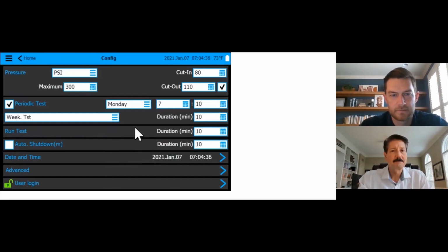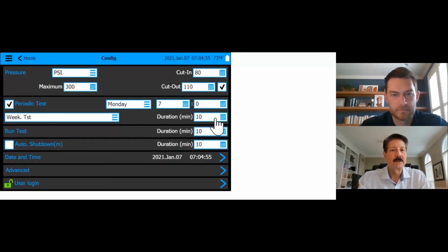Let me just look at this real quick. That first one, Marty, that's the hour, and then the second one is the minutes. Correct. So right now I've got it set for 7 a.m. in the morning, or I'm sorry, 7:10. Yeah. Obviously. I think we just keep it. So it's 7 a.m. in the morning, and the duration will run 10 minutes. So every Monday of every week at 7 a.m. in the morning, you're going to have a weekly test. It's going to turn the unit on. It's going to run for 10 minutes. It's going to shut down. It's going to record it as a test.